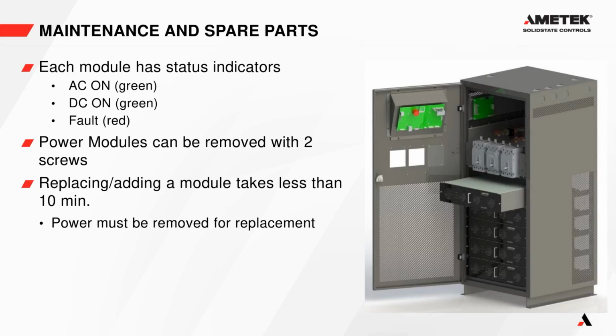Each module has 3 status indicators. We have an AC on indicator, which is a green light, a DC on, which is also green. And if there are any faults, you'll have a red LED that either is on solid or flashes, depending on the status of the system.